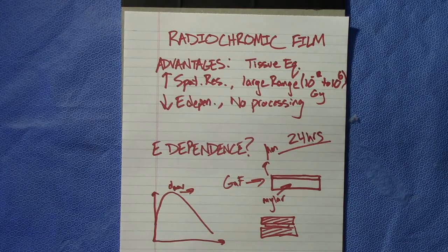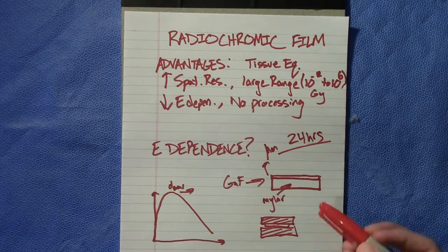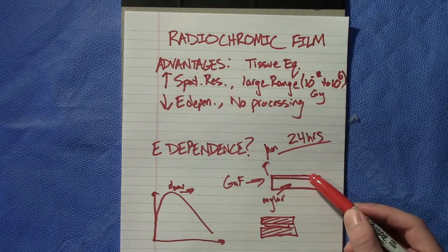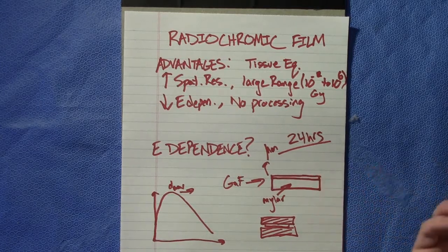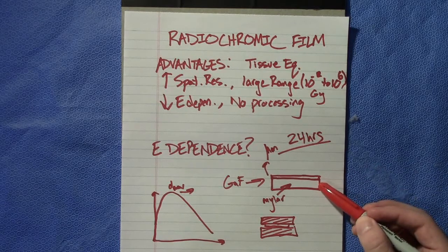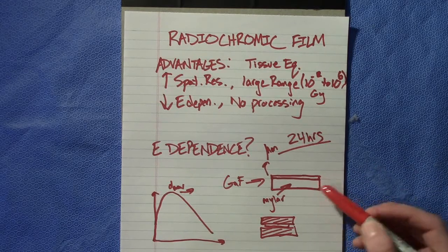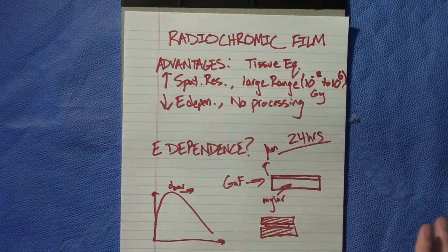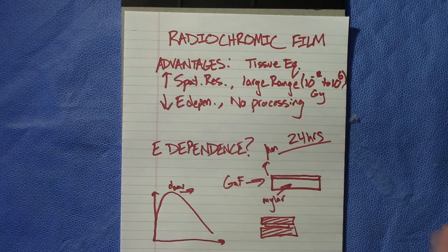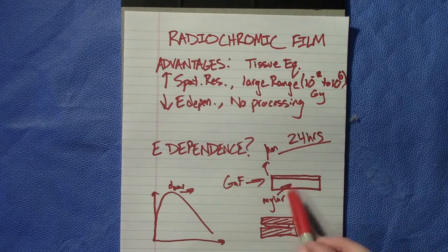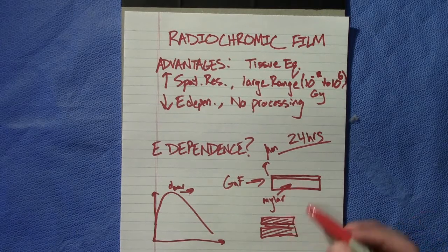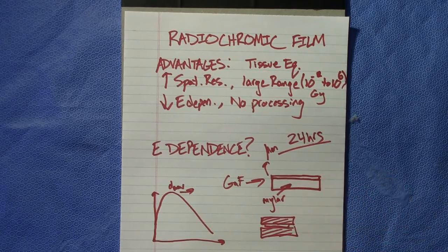Also, the calibration curve must be made per batch. Typically, you purchase a batch of film, and it comes with 24 films in there, something in that range, and you need a calibration curve for each batch, not just the same brand or the same type of film, but for each individual batch. And this turning of blue, the dye, that is a linear relationship with dose.